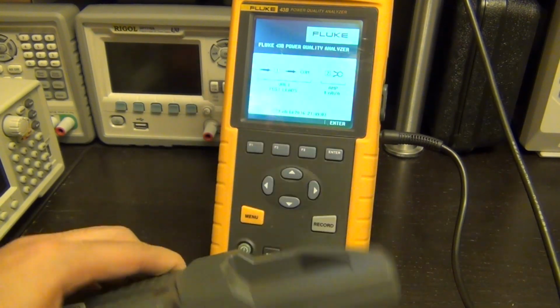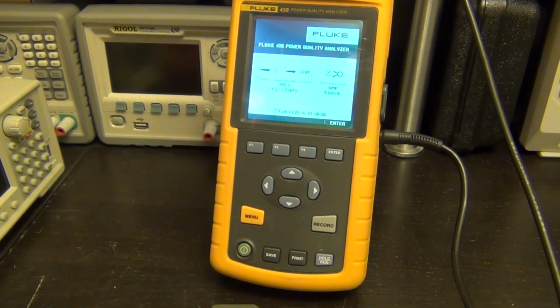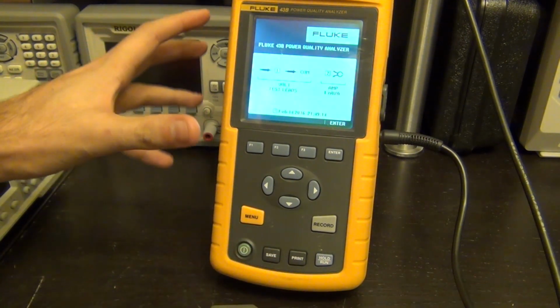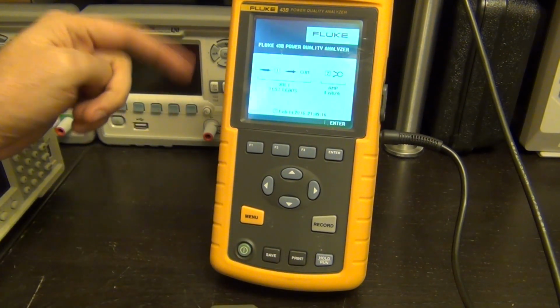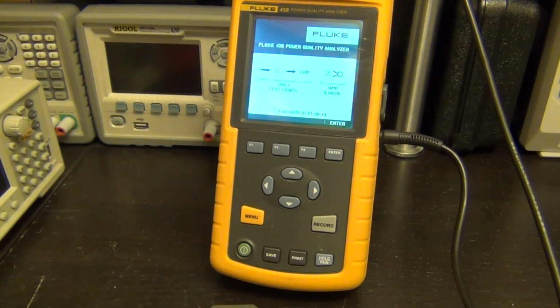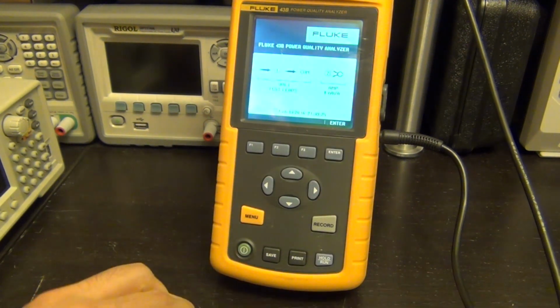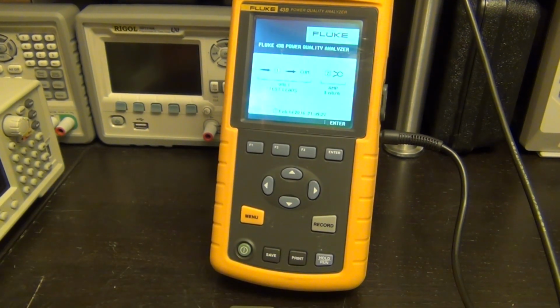Now I want to do a very quick measurement of some of these fluorescent lamps I have in the lab, because they're actually quite bad in terms of their power factor. The reason is because of the way they operate, and I'll explain that briefly once we turn it on. So I'm going to go past my light that's right now on in the room, directly through here.